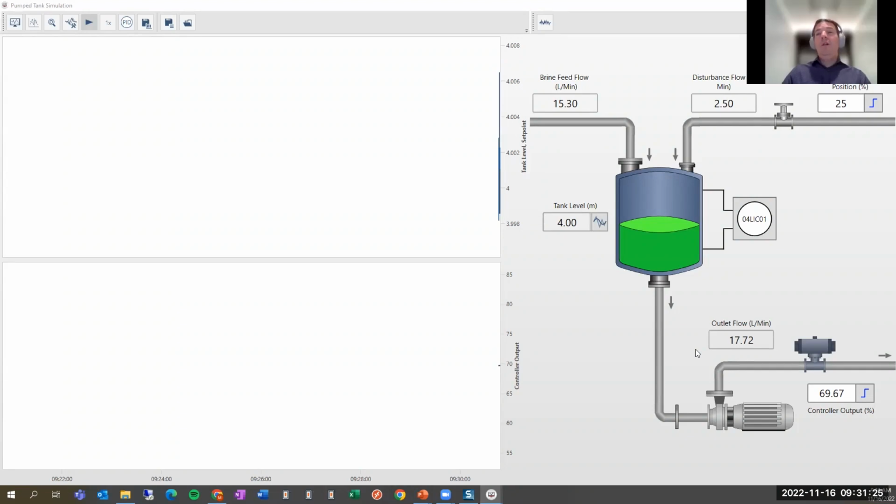No, I want to comment on the overshoot. We're in a level, in a tank, so I'm assuming you're not doing a set point change. Let's say you go from 50 to 60 and you don't want overshoot. I don't really believe that's happening. Usually you have a fixed set point and disturbances will come in. As I said, aggressive gain will minimize the disturbance rejection. If you really don't want any disturbance, that's where you will use a feed forward. You know that water will be added at a certain time, and then you can offset it with a feed forward on your pump, something like that. But set point changes, we don't see that much in tanks at all.